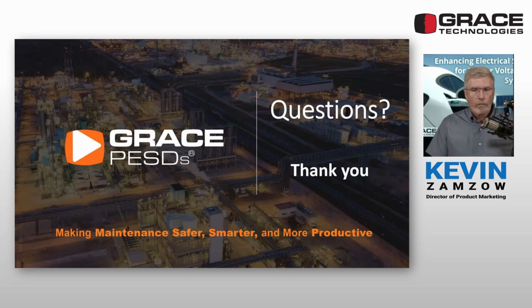Another question here. Can you provide an estimate of when the 1,000 plus volt products will come to market? What IP ratings and vibration resistance will they have? So we're anticipating by the end of next month, early August, we'll have production level quantities of the 3,000 volt versions of the products. We have samples, and we can have samples available sooner. We've completed our UL testing of the devices. They are rated to IP69K, similar to our 1,000 volt versions of the products. And as far as vibration, I don't know the vibration spec. I'll have to get that to you.